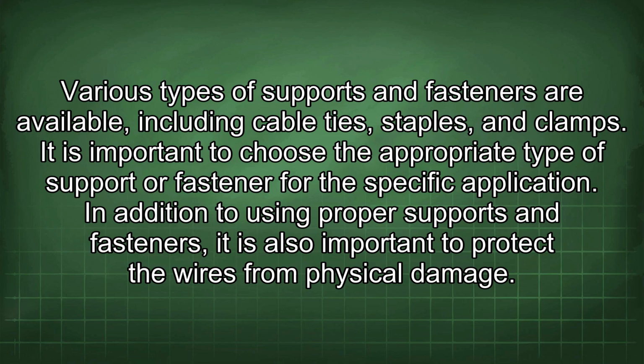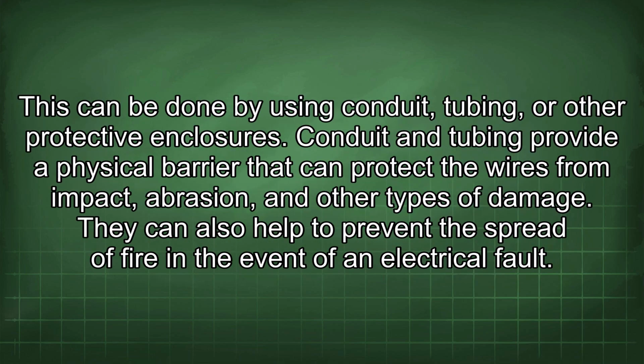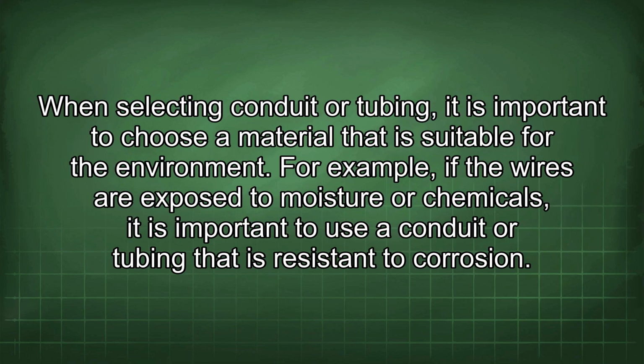In addition to using proper supports and fasteners, it is also important to protect the wires from physical damage. This can be done by using conduit tubing or other protective enclosures. Conduit and tubing provide a physical barrier that can protect the wires from impact, abrasion, and other types of damage. They can also help to prevent the spread of fire in the event of an electrical fault. When selecting conduit or tubing, it is important to choose a material that is suitable for the environment. For example, if the wires are exposed to moisture or chemicals, it is important to use a conduit or tubing that is resistant to corrosion.